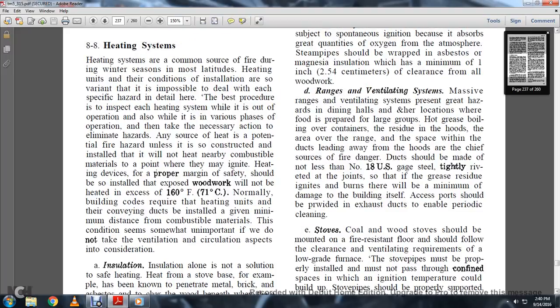8.8. Heating systems are a common source of fire during the winter seasons. In most latitudes, the heating units and the conditions of the installation are such that it is impossible to deal with each of the specific hazards. The best procedure is inspect each heating system while it is out of operation. Although various phases of the operation take the necessary action to eliminate hazards, any source of heat is a potential fire hazard unless it is constructed and installed so that it will not heat nearby combustible materials to the point where they ignite. Heating devices should be installed with a proper margin of safety, so that exposed woodwork would not be heated in excess of 160 degrees Fahrenheit.